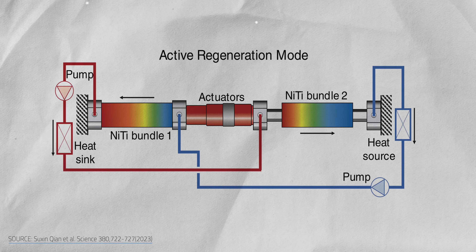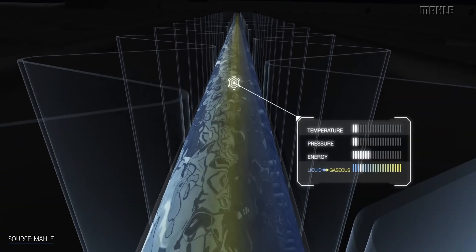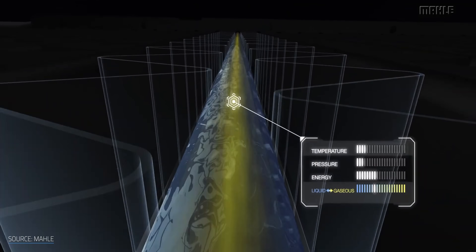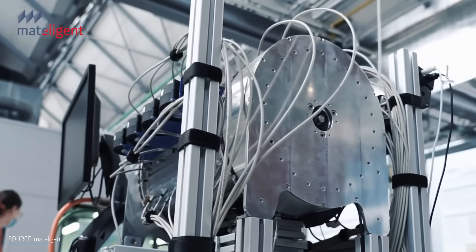To be clear, like with other solid state tech, solid state doesn't mean there's no liquid or moving parts in this context. While caloric cooling doesn't require refrigerants, you obviously can't pump a solid material through a system. You still need a mechanical input, like a linear actuator, to get things moving. So depending on the design, a caloric cooling system might still need a heat transfer fluid to deliver that freshly cooled air where it needs to go — and in fact, some elastocaloric prototypes do use fluids.